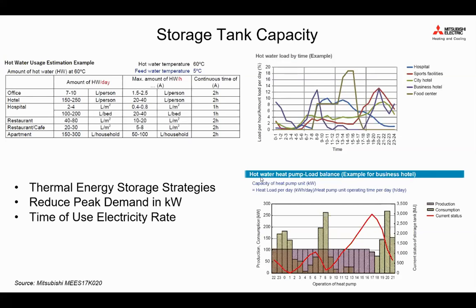required. So let's say for a hotel, or even for an apartment, you will need about 150 liters to 300 liters per household per day. The maximum hot water requirement is about 50 to 100 liters per household per hour, and then a continuous runtime of maybe 2 hours.